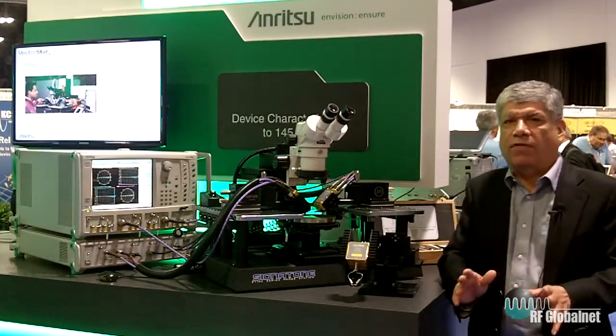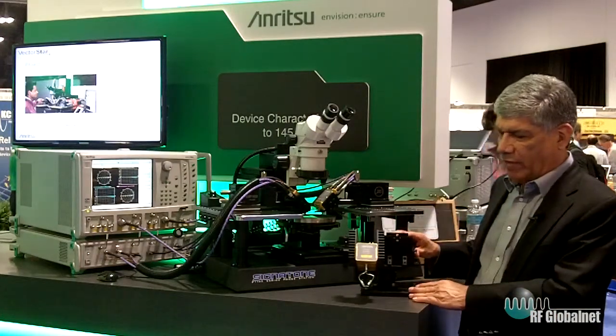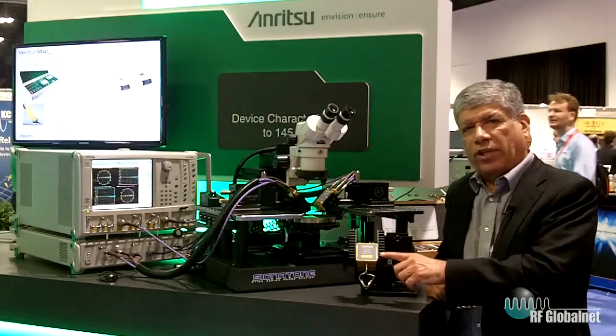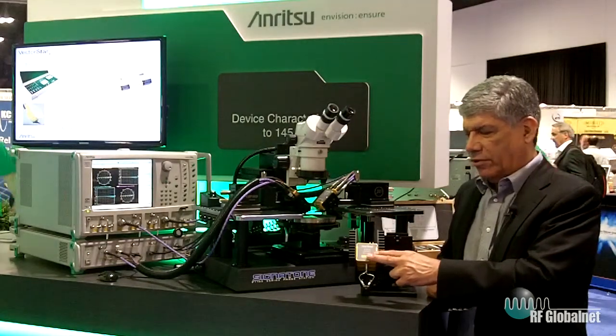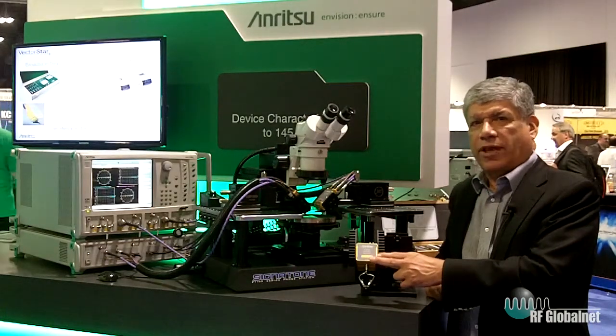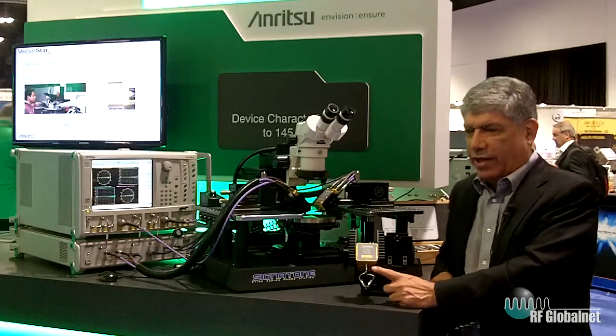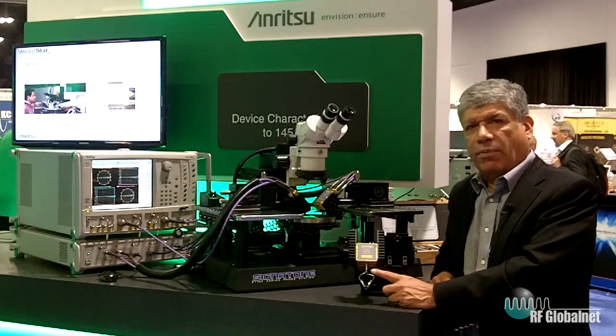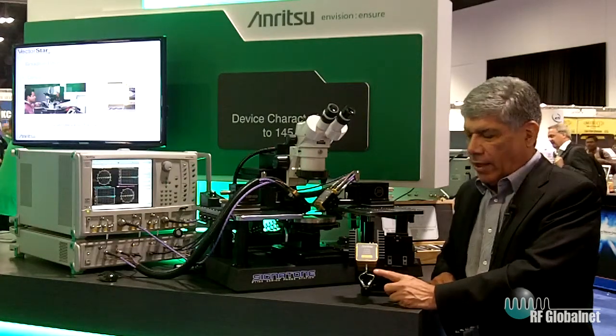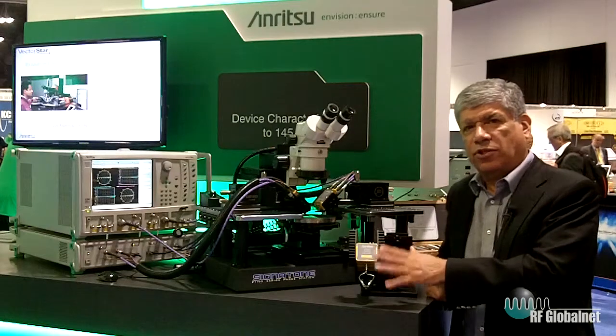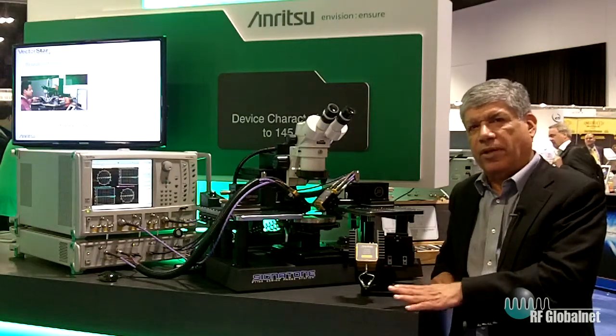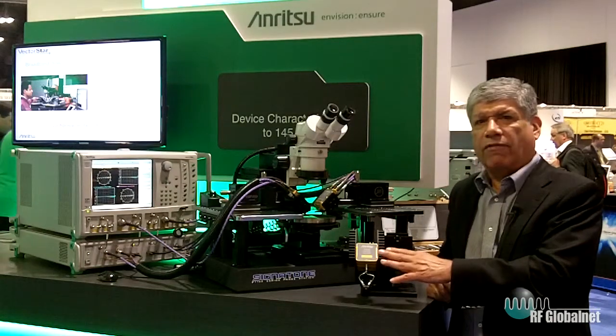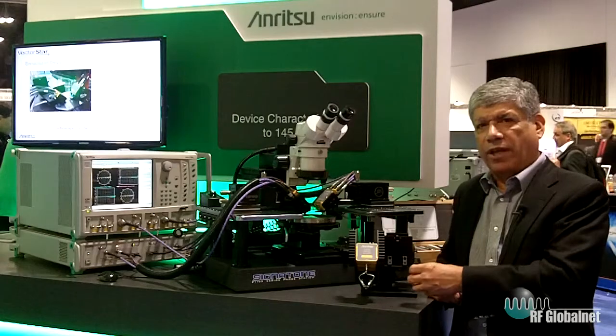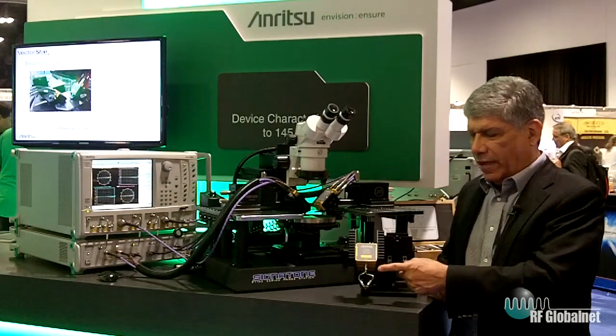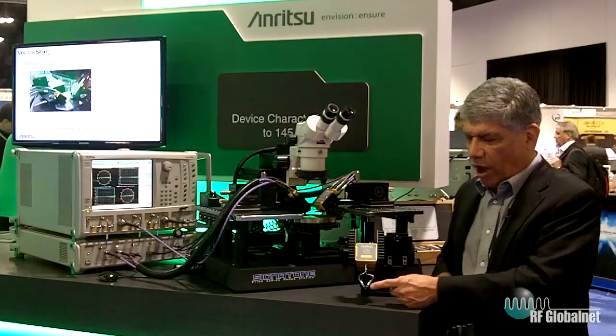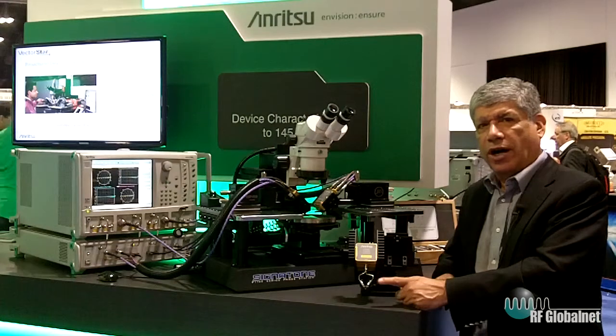And that's basically coming off of the previous modules that we have been developing that goes to 110 and 125 gigahertz. So the first introduction of the nonlinear transmission line modules went up to 110 and 125. And they distributed their signal test port in a 1 millimeter connector. And the fact that we were able to make the module so small with very high RF performance and very good stability has given us a number of options in terms of setup and configuration. So you can see with the 110 modules that we have a differential setup driving a differential probe going all the way up to 110 gigahertz.